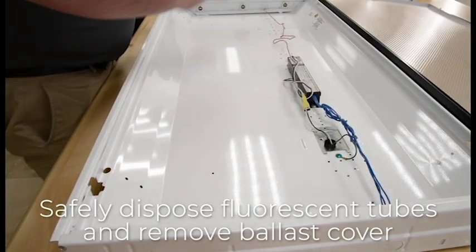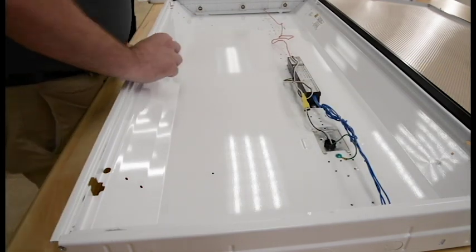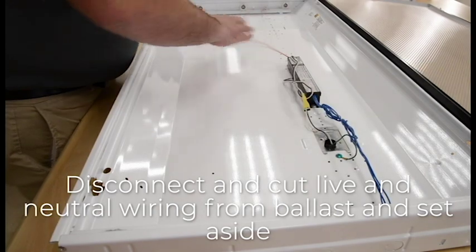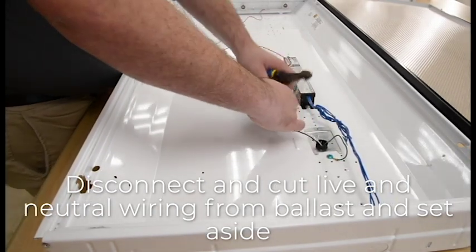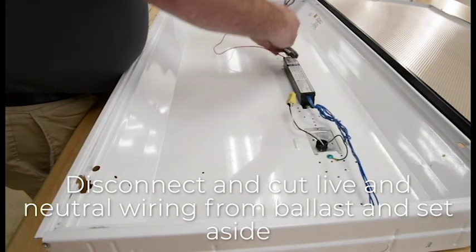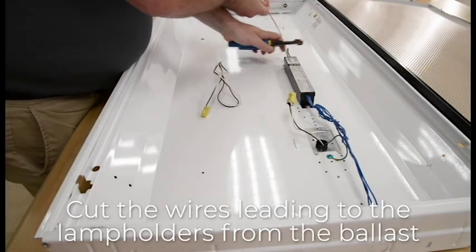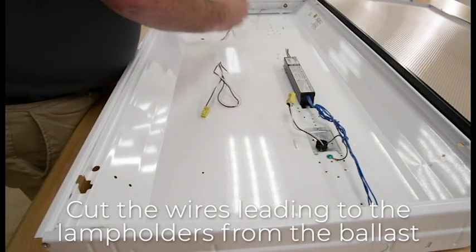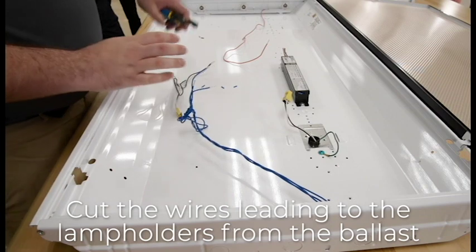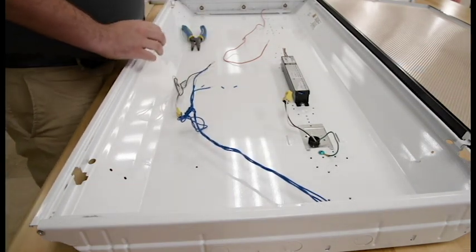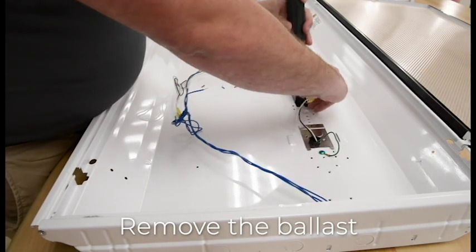Safely dispose of the fluorescent tubes and remove the ballast cover. Disconnect the wire clip connecting the ballast to the main power source, then cut the live and neutral wiring from the ballast. Cut the input and output wires that lead from the lamp holders to the ballast. Now you can remove the ballast from the fixture.